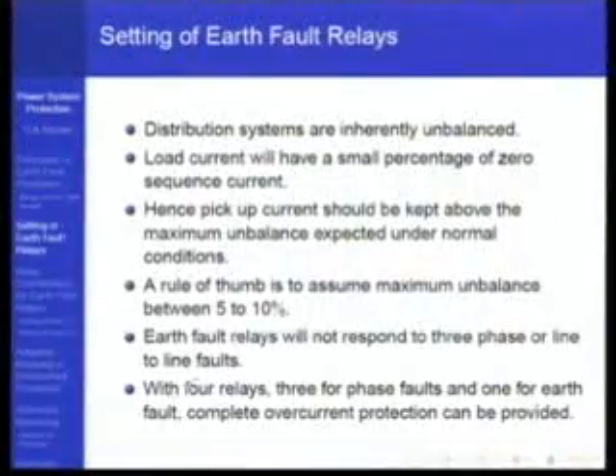Okay, so a rule of thumb is that 5 to 10% is an unbalanced current in a system. As I said, an earth fault relay picks up on zero sequence. So if 100 amperes is the full load current, and the system has an unbalance of 5 to 10%, then the earth fault relay pickup current should be above 10 amperes. It cannot be below 10 amperes.